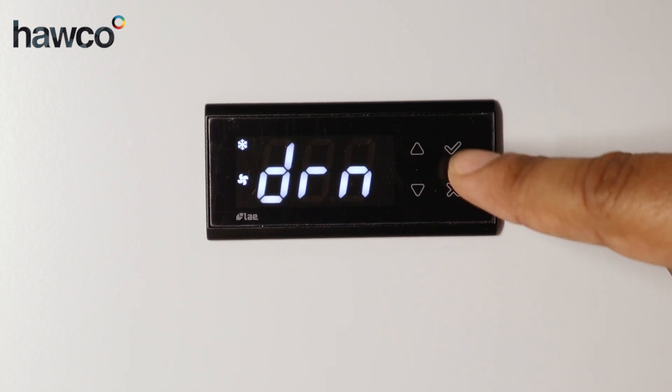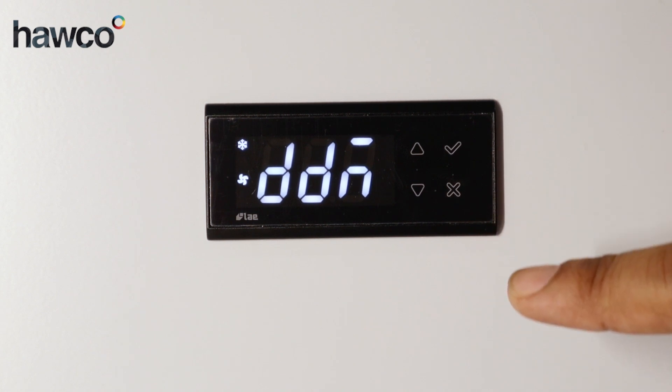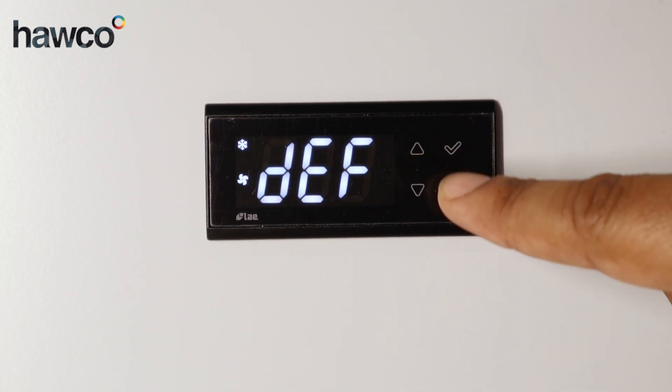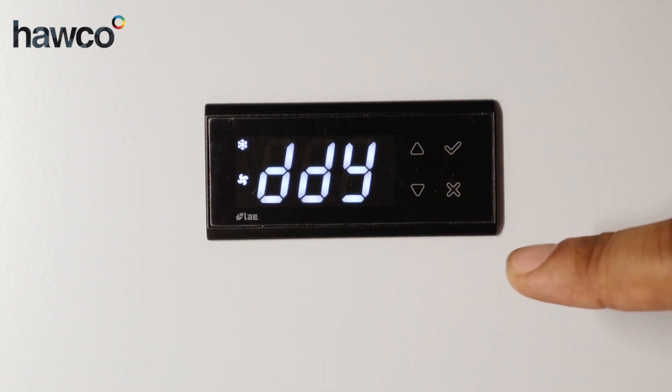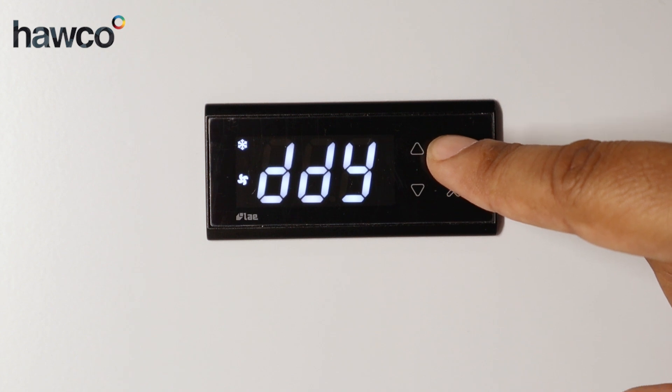DRN, which is drip time, set to zero. DDN, which is set to display during defrost, is set to DEF. DDY is a step for the delay for the display, which is set to three minutes delay.